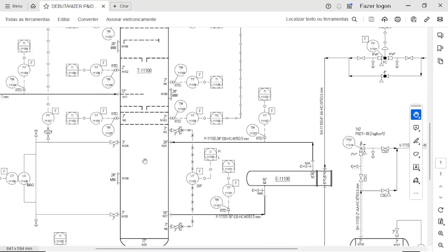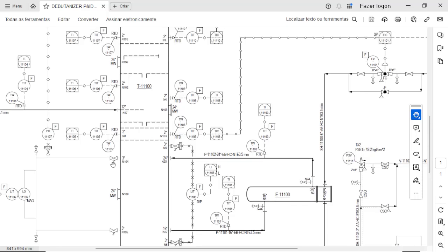This kind of information sometimes is not shown in the pipe instrumentation diagram because I can infer it from this valve here, for instance, a 3 inches isolation valve. If I connect to a nozzle, it is the same size. So I eventually don't need to show these 3 inches because my nozzle already shows me that it's connected to a 3 inches valve. And the nozzle number sometimes is not shown in the pipe instrumentation diagram because it's information for the mechanical drawing of the equipment.